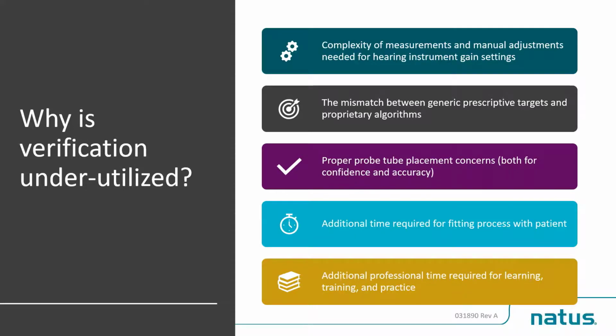So why is verification underutilized? It sounds like a lot of you are verifying, so that's fantastic. But why are some clinicians leery of following some of these best practices? Sometimes it's a little more complex, and going through all the manual adjustments can be intimidating. Also, hearing aid manufacturers have proprietary fitting algorithms versus our evidence-based NAL and DSL targets. Also, in the beginning, when you're first learning how to place a probe tube, it can be a little unnerving. Sometimes you're afraid you might bump the patient's eardrum, make the patient uncomfortable, and wonder if you're doing that correctly. It may also add a little bit of time initially to the fitting visit, and then there's the extra time and expertise, CEU follow-ups, and things we have to do to make sure we're fresh on all of that information.